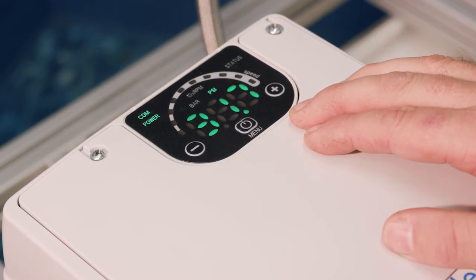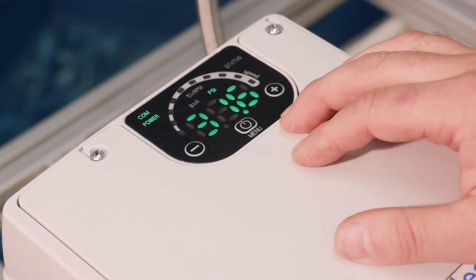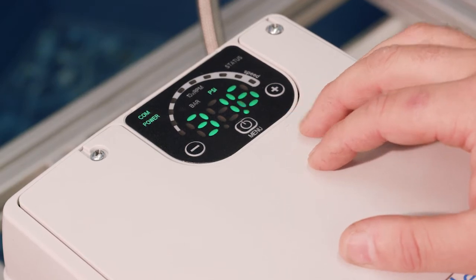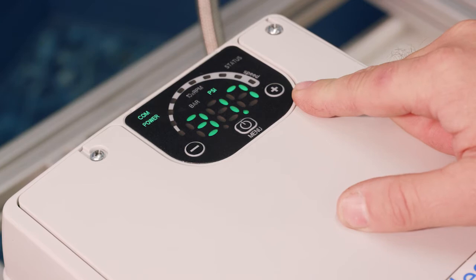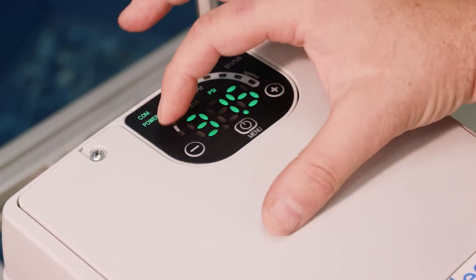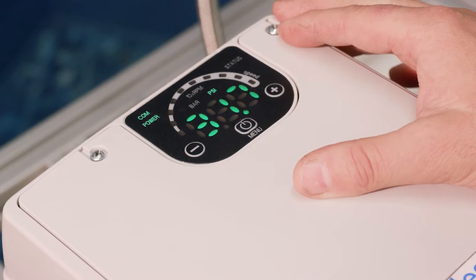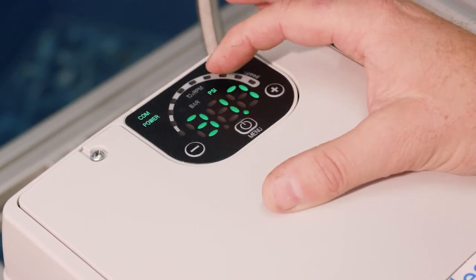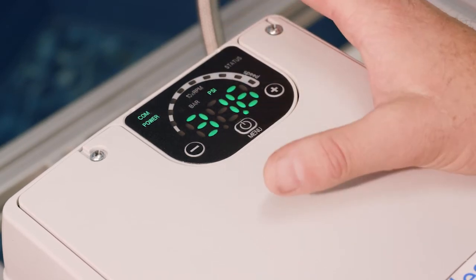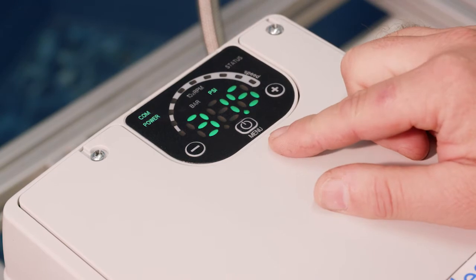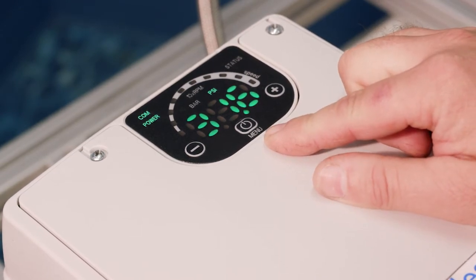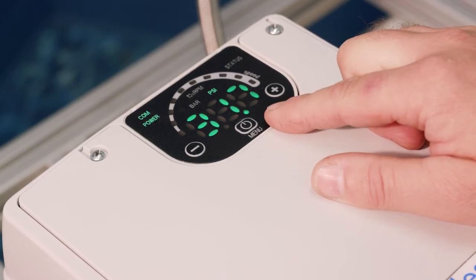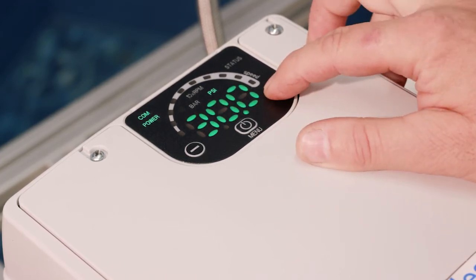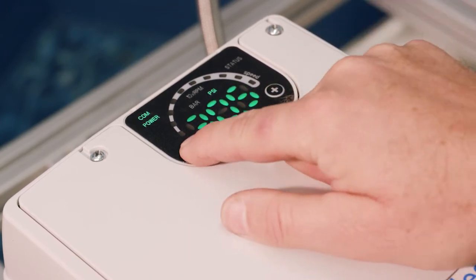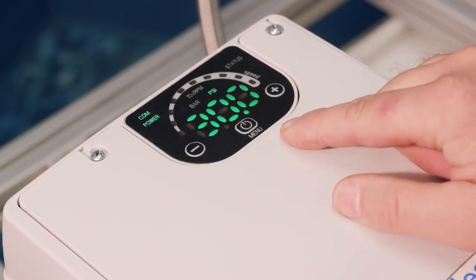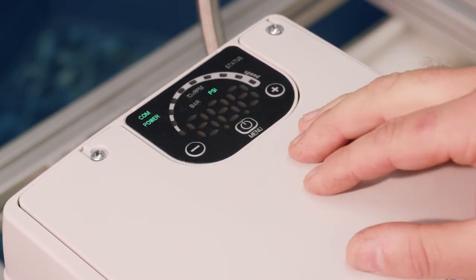Let's take a quick look at the keypad in the smart pump design. Very simple, and we can see here we have a minus and a plus button and a menu button. Across the board here, we are able to look at 2 different things: PSI and RPM. The one really nice thing about this drive is it's very simple to change the pressure. You don't have to go into any of the parameters. You simply hit the plus or minus button to change your pressure. All right, so we'll just set it at 30, and as far as setting the pressure, that's all you have to do.